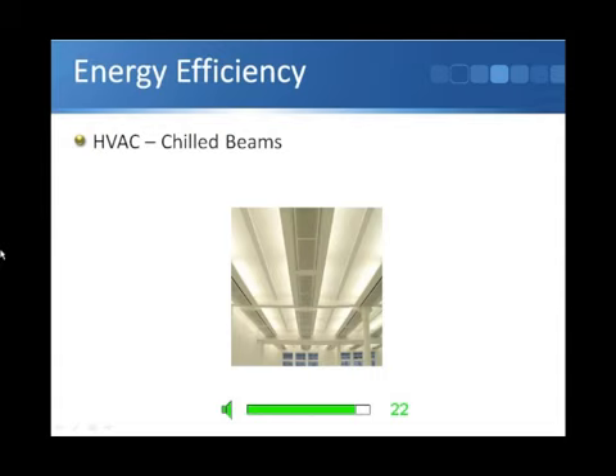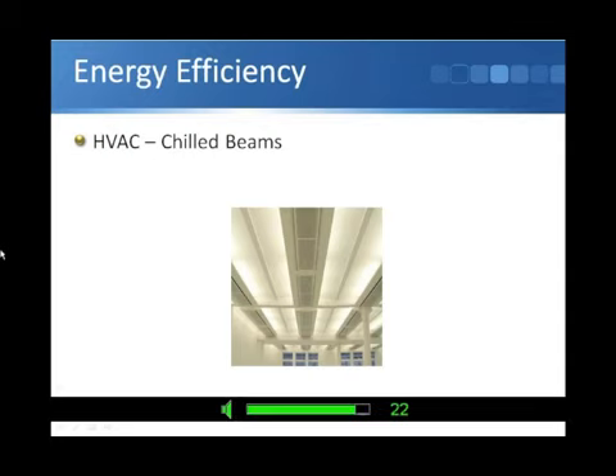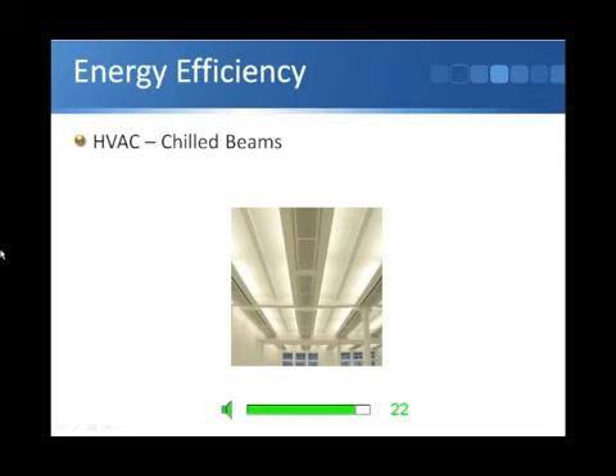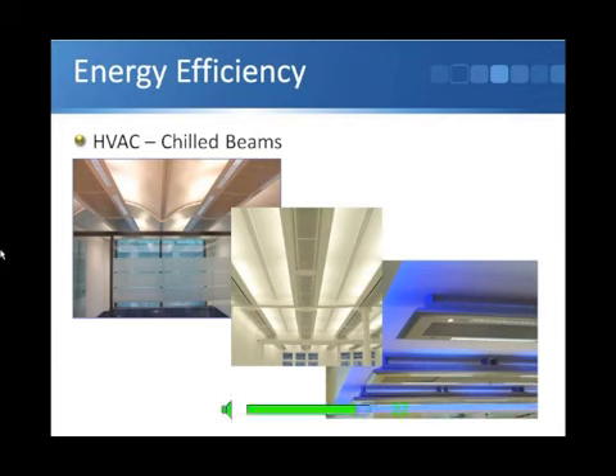Another approach that's been very effective in Europe and is now seeing a lot of use in the United States is chilled beams, and this is where we bring cooling water in, chill air at the top of a room, and that air is cooled and drops back into the occupied space. But the significant thing here is that the chilled water we're using is up at about 14 to 15 degrees C, above the dew point temperature, obviously. And that allows us to run cooling systems at a higher temperature, where we have more efficient operation of the plant, better COPs on our heat pumps and so forth. So a couple of shots of different systems there.